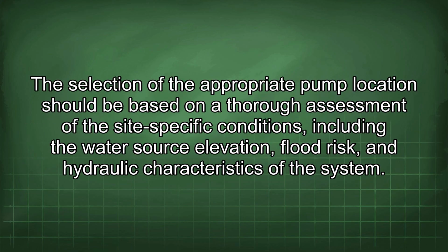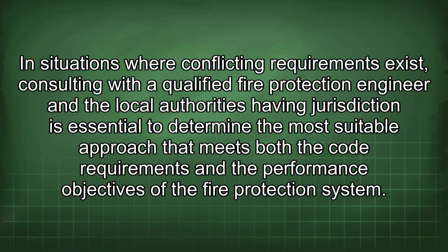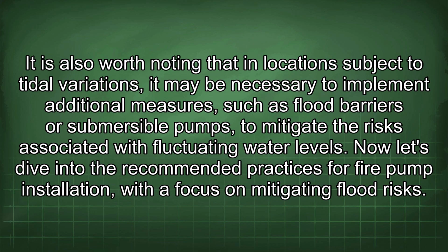The selection of the appropriate pump location should be based on a thorough assessment of the site-specific conditions, including the water source, elevation, flood risk, and hydraulic characteristics of the system. In situations where conflicting requirements exist, consulting with a qualified fire protection engineer and the local authorities having jurisdiction is essential to determine the most suitable approach that meets both the code requirements and the performance objectives of the fire protection system. It is also worth noting that in locations subject to tidal variations, it may be necessary to implement additional measures such as flood barriers or submersible pumps to mitigate the risks associated with fluctuating water levels.